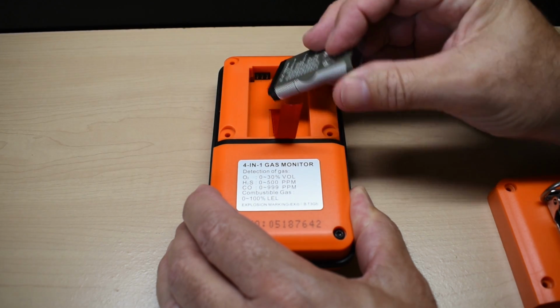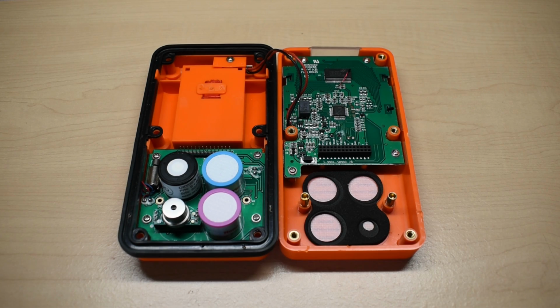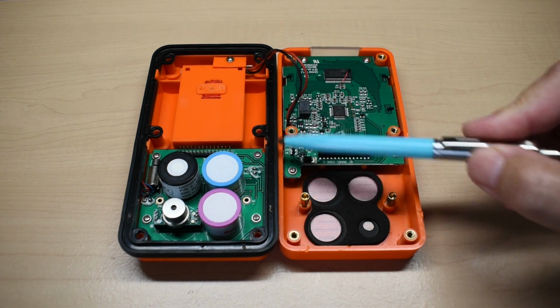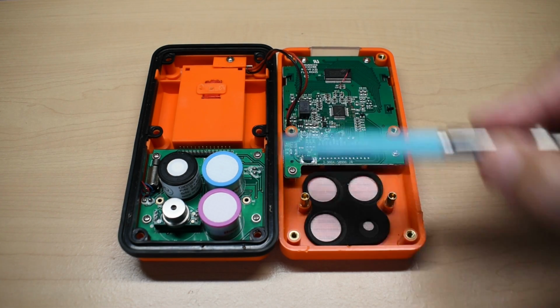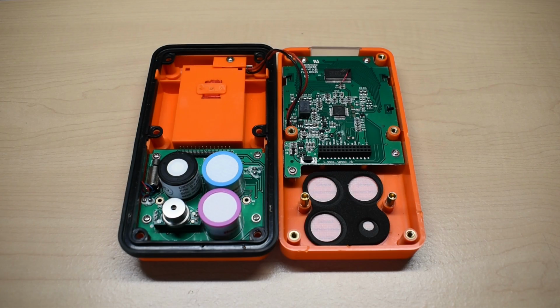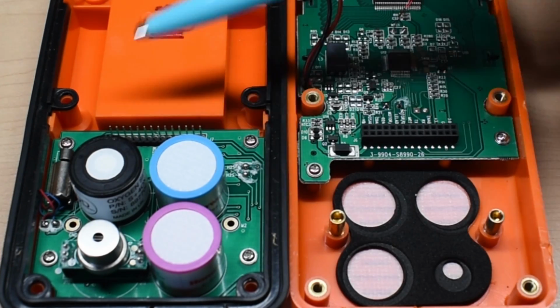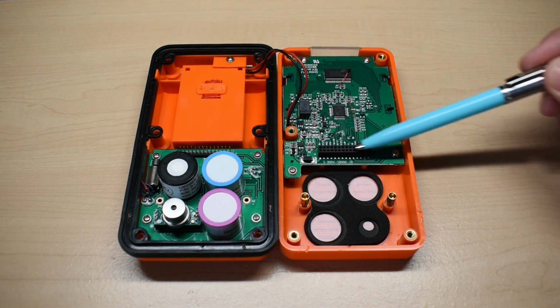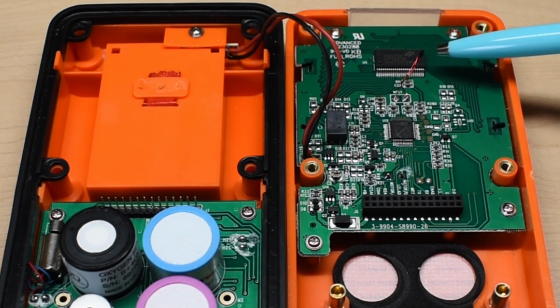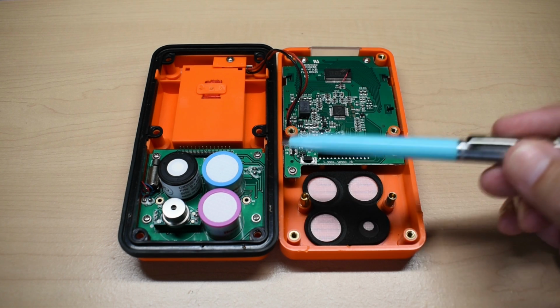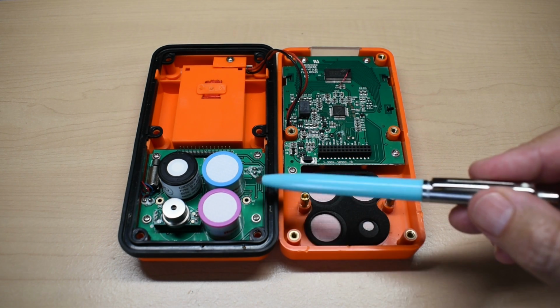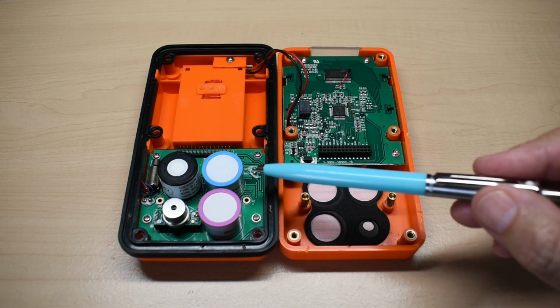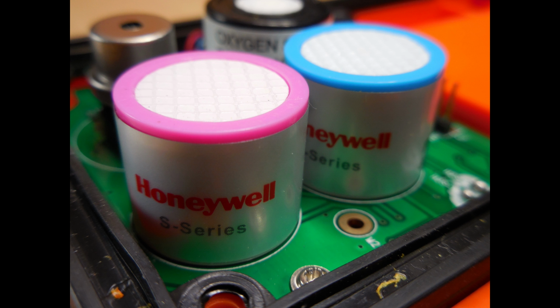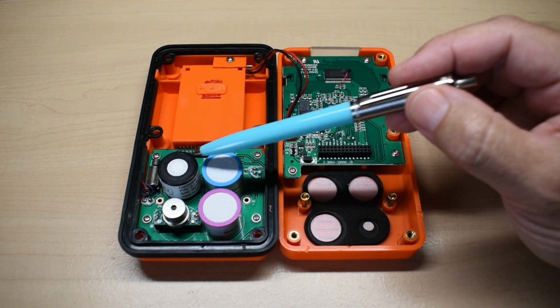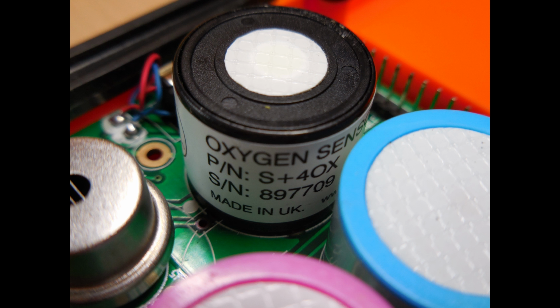Maybe 9-10 millimeters. Okay, here's what it looks like after a little bit of a struggle trying to separate both halves. I have the rubber seal, goes around the perimeter. You can see the sensor board has this pin header, plugs into over here. This board has a little bit of a temperature sensor right on top of that integrated circuit. And what I really like is that these two sensors here, the carbon monoxide and the hydrogen sulfide, are made by Honeywell, and this oxygen sensor is made in the UK.